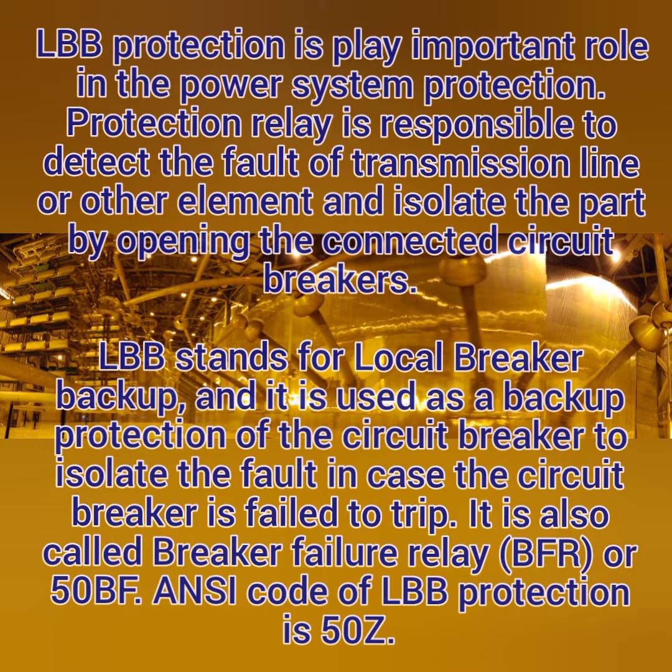Welcome to my channel. In this video, we are going to see more about the LBB protection. Normally, the LBB protection is a backup protection and it stands for local breaker backup. It is used as a backup protection of your circuit breaker to isolate the fault in case the circuit breaker fails to trip. It is also called a breaker failure relay or 50BF for short, and the ANSI code of the LBB relay protection is 50Z.